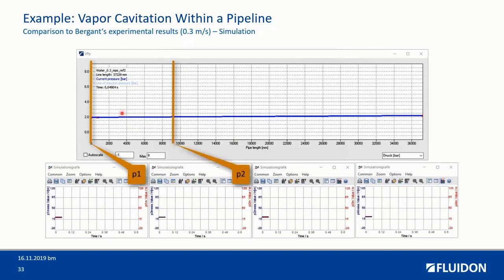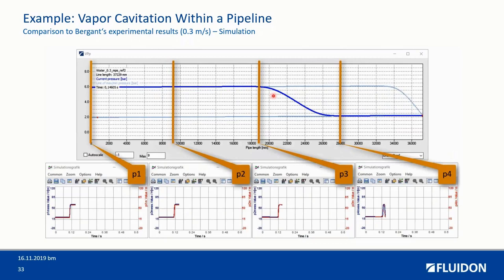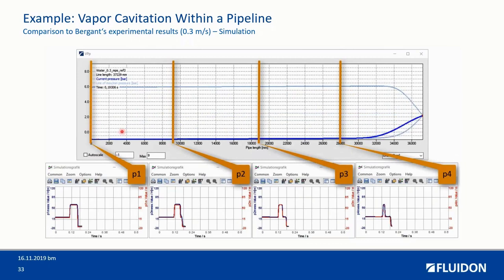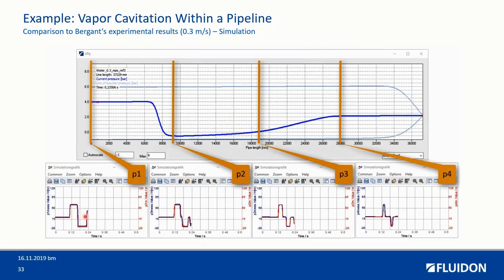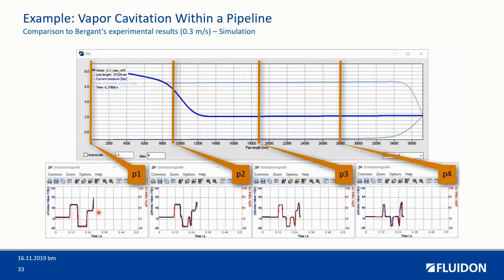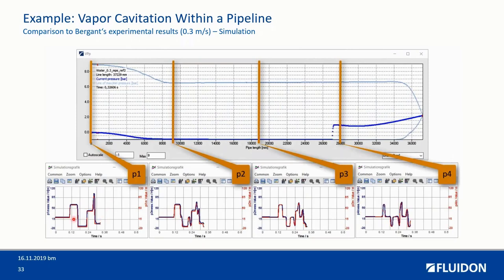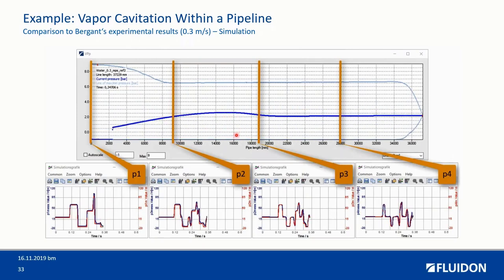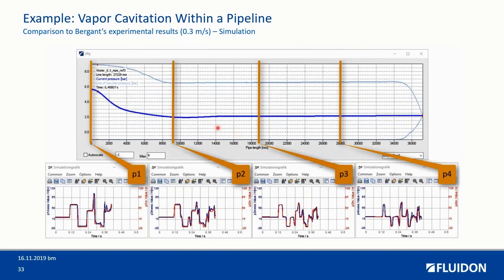So what you see here — we are at 0.05 seconds. Soon the valve will be closed and we see a sharp increase in the pressure, and now the pressure wave travels backwards, is reflected at the open end, and travels back to the closed end where it again is reflected but in a different way since that is a closed end. This creates a suction wave with cavitation. On these diagrams, in blue you see the actual measurement provided by Bergant, and in red you see the simulation result with DSH-Plus.